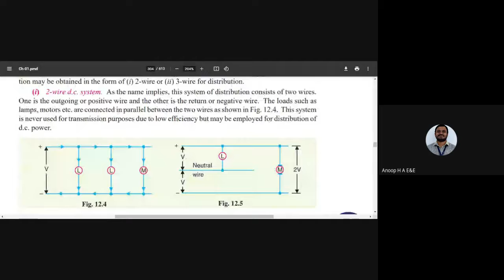Let us understand what a 2-wire and a 3-wire distribution is, depending on the circuit diagram here. In a 2-wire system there are positive and negative wires. If lamps are connected, they draw current and the lamp is turned on, or a DC motor connected there can be used. Next, you have one more wire called the neutral wire. This neutral wire is introduced such that, for example, in a 2-wire system you have 220 volt. So what would be the voltage in a 3-wire system if it is at the midpoint?